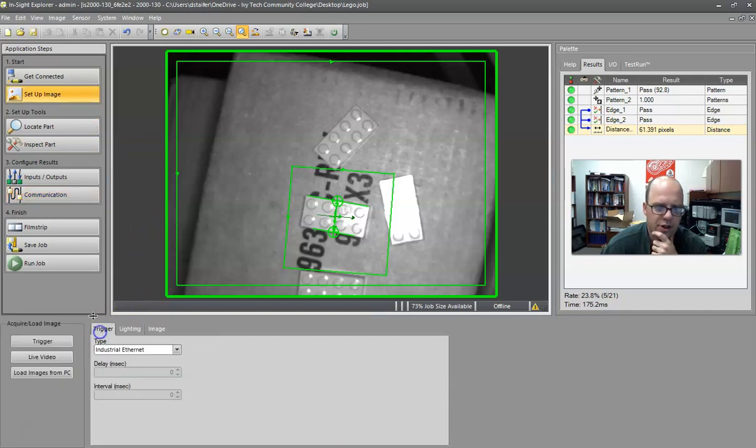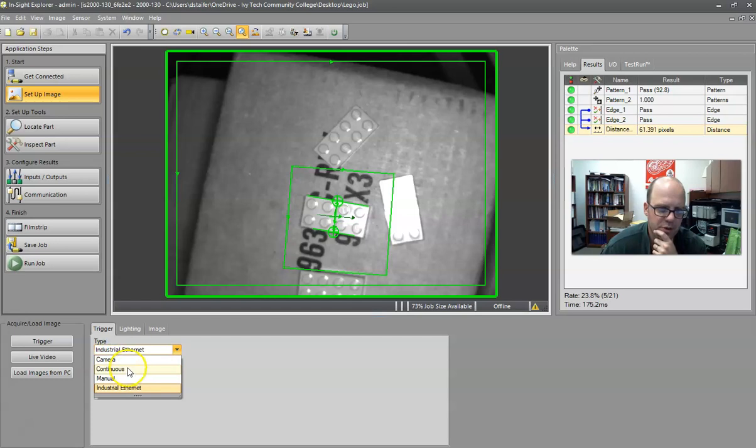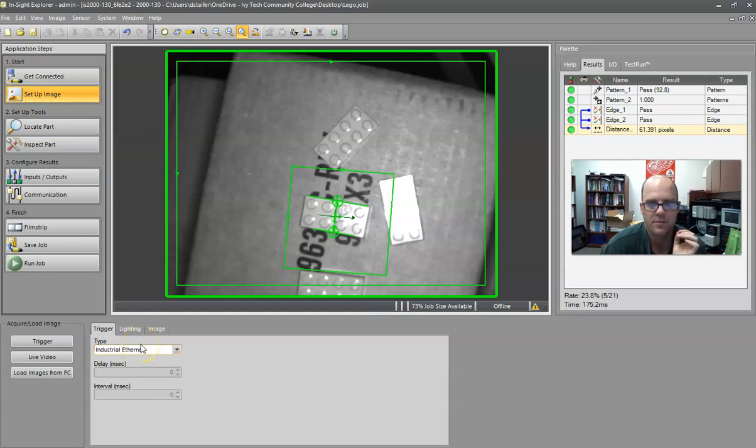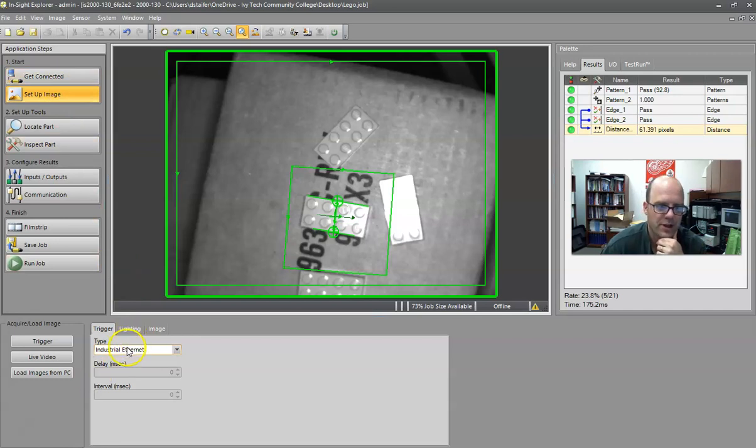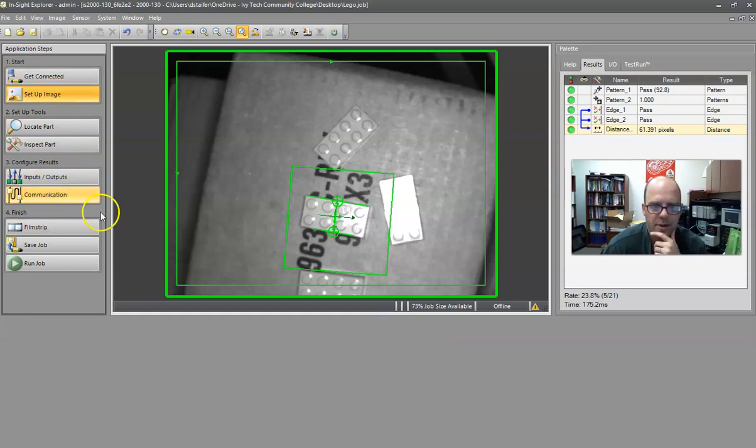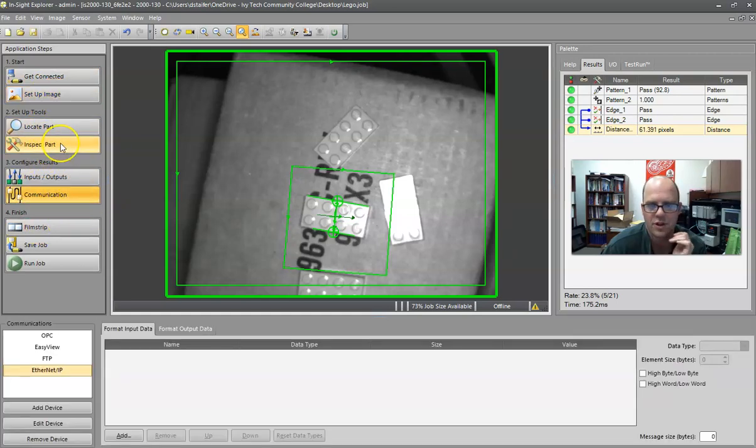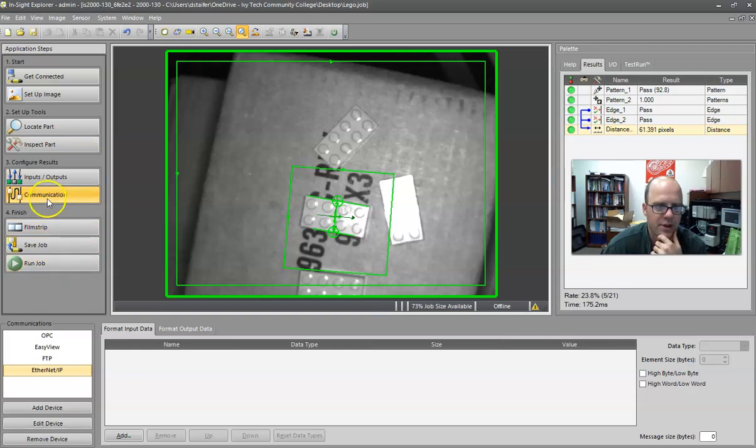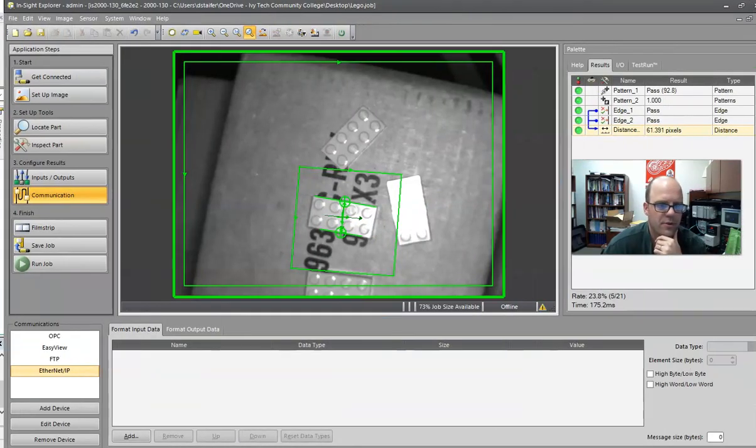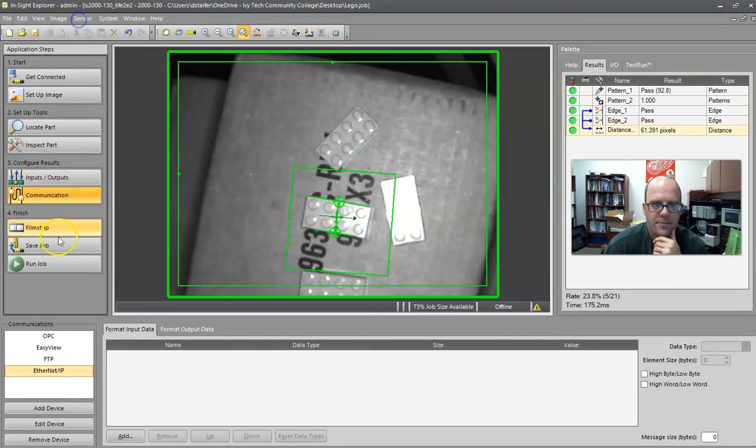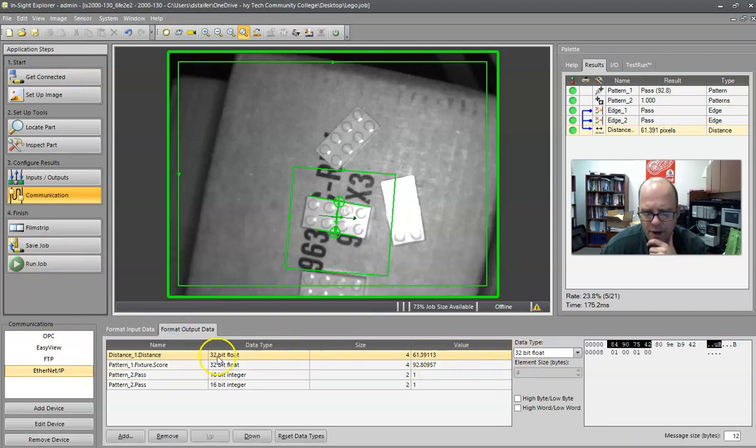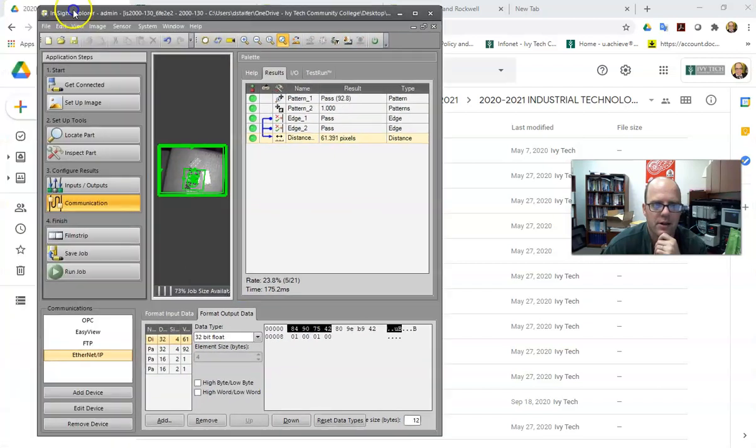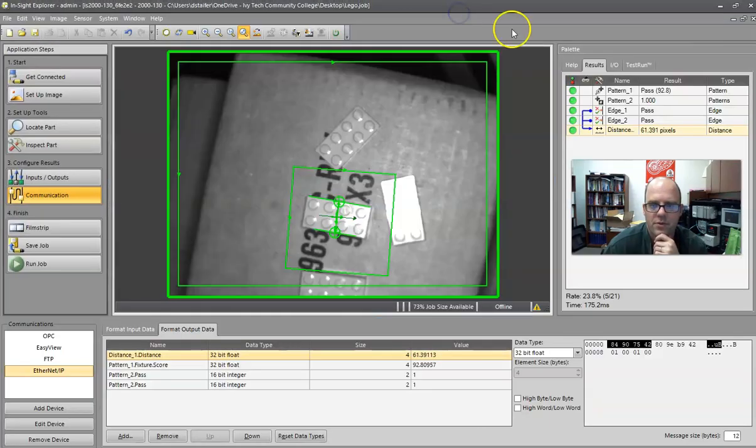Yeah, that's it. Set up image under trigger. What type of trigger you can do. Continuous, you can do something on the camera, you can do manual. I have it through industrial Ethernet, so I can actually trigger the picture from my PLC. Okay, so make sure that is set up there under setup image and then the communication. Otherwise, the setup tools, the inspect tools, that stuff done in another video much better than what I can do. But that's some basic setup communication. I'm going to go back to Studio because now that I, so, sorry, now that I see this, make note of the fact that I have a float, a float, an integer, an integer. Okay, that's going to come in important because we want to set up a user-defined data type so we can process that data in our information.